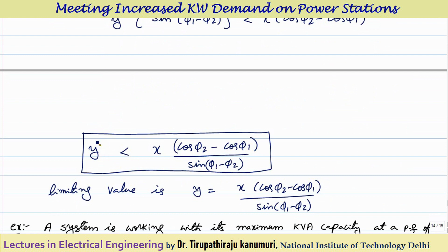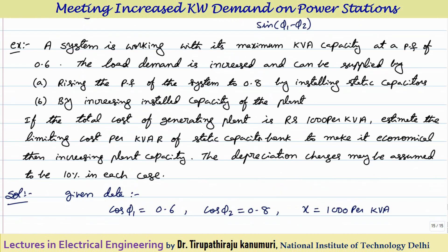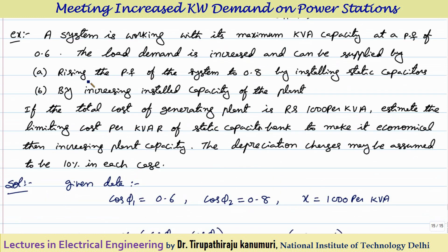So the cost per KVAR of power factor improvement equipment, Y, should always be less than X × (cos phi 2 − cos phi 1) / sin(phi 1 − phi 2) for it to be economical. The limiting factor occurs when Y equals this value — meaning whether you expand the power plant or install power factor improvement equipment, there is no economic difference. Let us take an example to understand this concept.